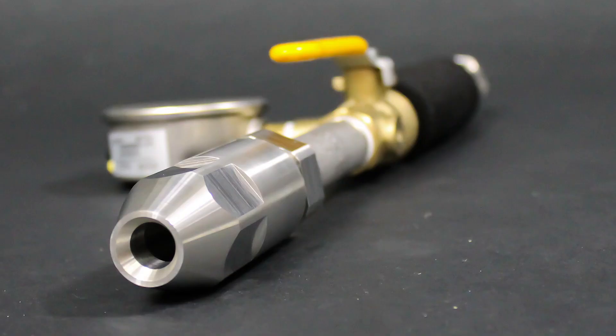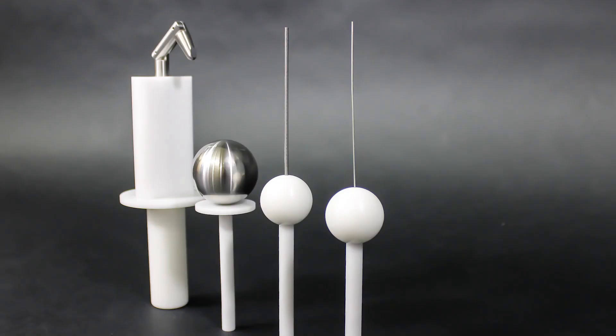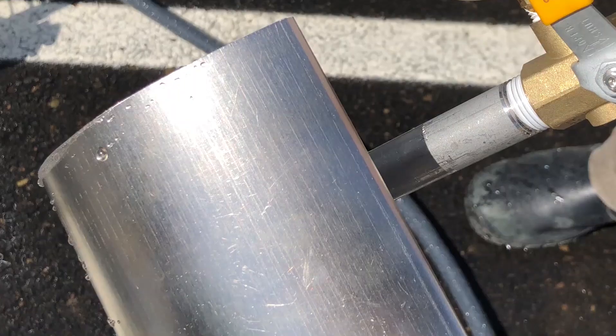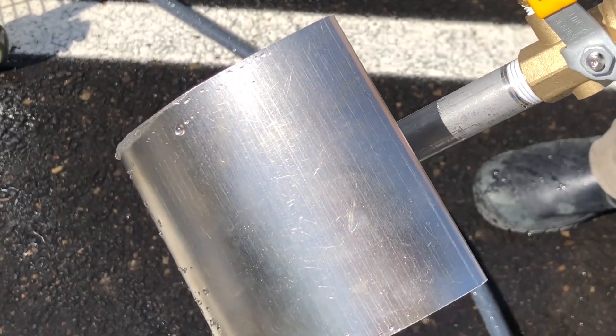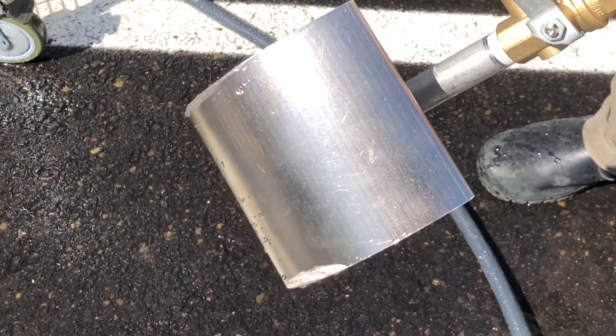These pieces of test equipment that we built in-house allow us to test two IP ratings, and those IP ratings are defined by the IEC 60529 standard. These pieces of test equipment allow us to test for both particulate ingress and water ingress.